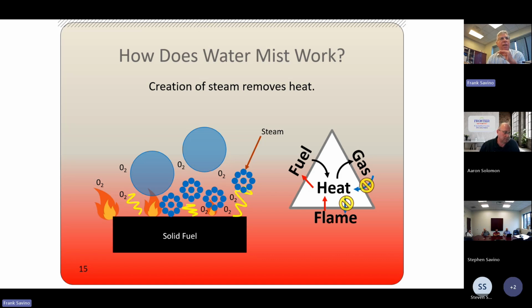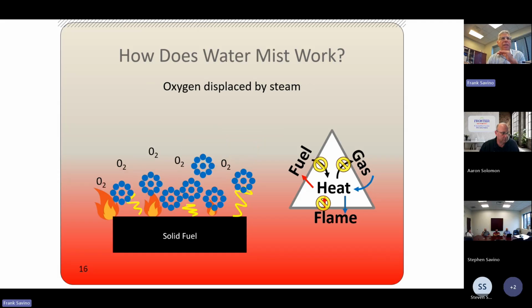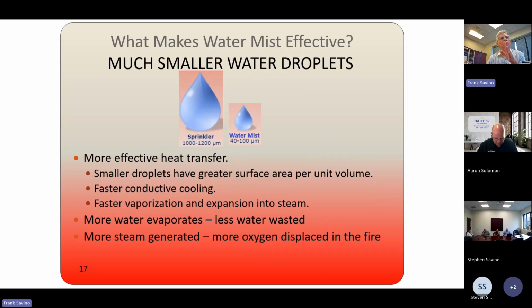So again, the way it works, the creation of steam removes heat through the heat of vaporization principle, and displaces the oxygen away from the fire through the production of steam. So why does that happen? Okay, well, because of the smaller water droplets, you have more effective heat transfer. When you take a fixed volume of water and create smaller droplets with it, what you're really doing is increasing the surface area per unit volume. And really all transfer of heat happens at the surface. It doesn't happen in the middle. So when you're increasing the surface area of the water, you're increasing its fire extinguishing potential.